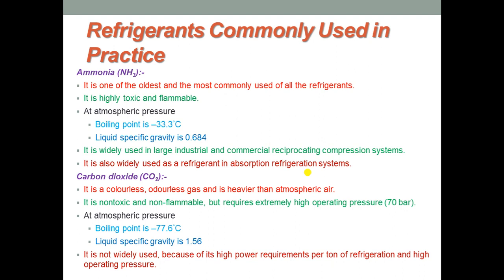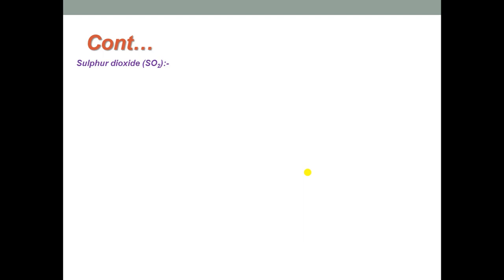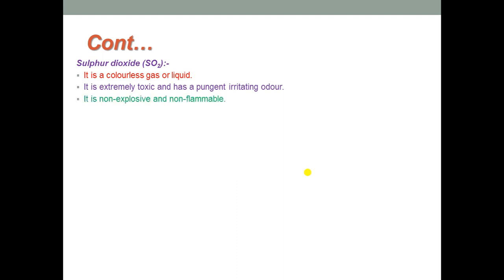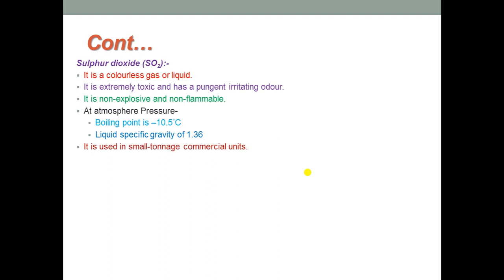Carbon dioxide is not widely used because of its high power requirement per ton of refrigeration and high operating pressures. The next is sulfur dioxide, the third common type of refrigerant. It is a colourless gas or liquid, extremely toxic with a pungent irritating odour. It is non-explosive and non-flammable, has a boiling point of -10.5°C and liquid specific gravity of 1.36. It is used in small tonnage commercial units.